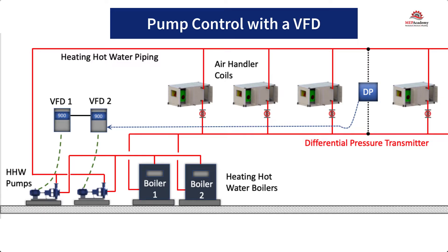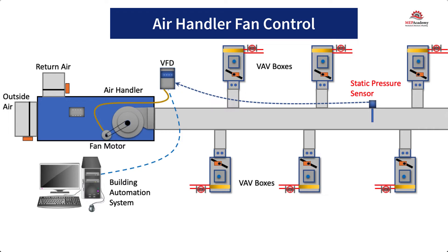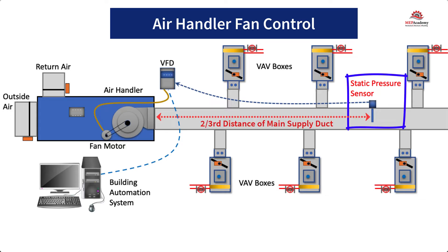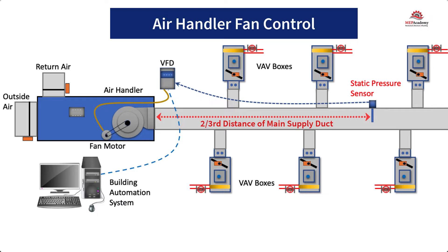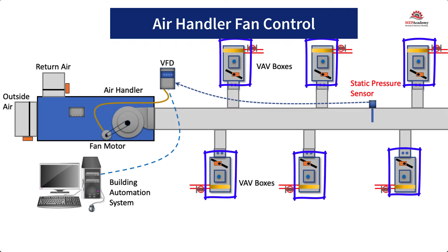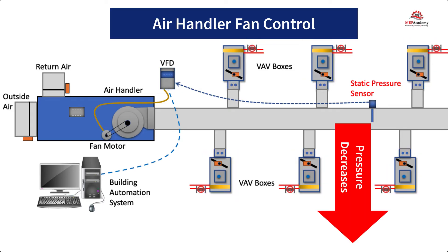The same thing is used for fan control. The theory is the same for controlling the speed of the fan motor. There is some form of monitoring of the supply air duct, which will cause an adjustment to the speed of the fan, the RPM. In the scenario here, a static pressure sensor is located two-thirds of the way down the main supply air duct. The sensor will pick up changes in pressure within the duct.